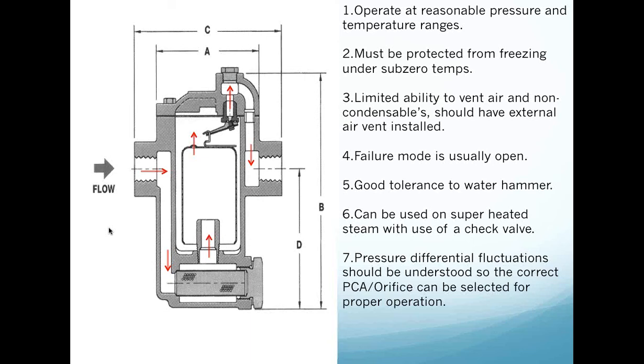If you are controlling with a control valve a zone, let's say for example a coil or a zone of coils that are heating air going over the top of a product, and the zone is controlled with a control valve, if that control valve will fluctuate to satisfy that zone, and all of a sudden we start to lose the steam pressure because we don't need the steam heat, then we lose the differential that helps push the condensate through the system. If that pressure starts to degrade, we also lose the ability of that pressure differential to help us process the condensate that we have banked up through the orifice in that trap.